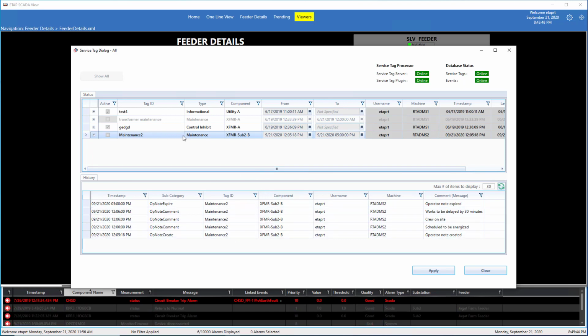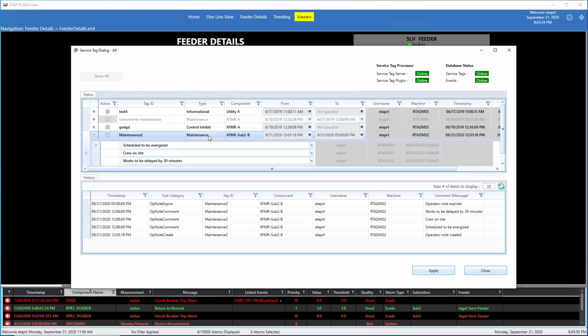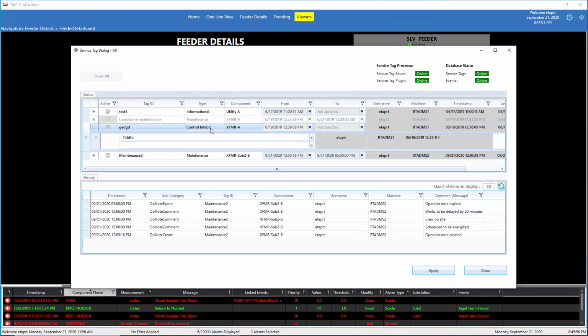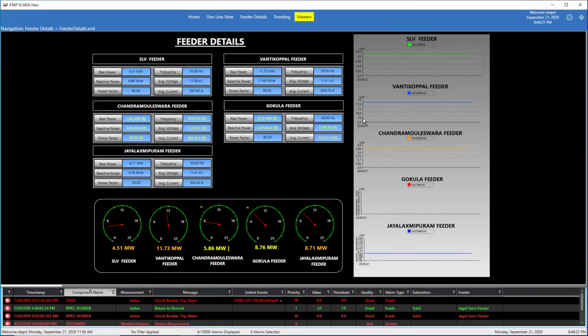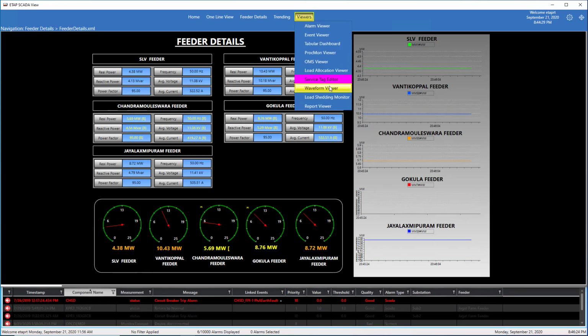Now, there are different types of tag-out. For example, this one is a maintenance tag, indicating that this transformer is under maintenance. There's also control inhibition. So if somebody is going to do work on the panel and you want to prevent any remote control, you can create a tag-out called control inhibit, and that will prevent the SCADA system, or even the ISO panel, from sending any remote control to open or close that device. So this is another tag-out information that is very important at the substation level.